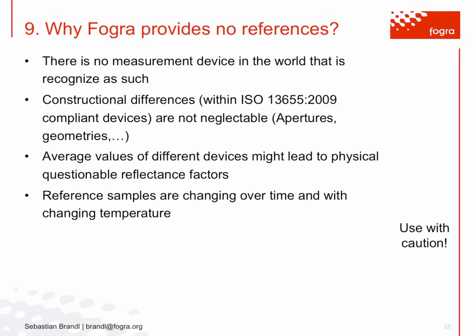If you use different devices and just average the LAB or reflectance spectra, that might not lead to physically useful spectra, because what we measure is the reflectance factor basically, and then all the other numbers are computed from it. So if you just use 3, 4 devices and average it and say this is what we call political averaging, then you can do it for certain circumstances, but this is not the right way to provide aim values for a device later to do a correction.